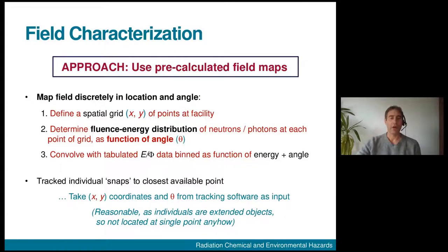So instead, the approach we used was to pre-calculate field maps. In other words, we mapped the field discretely in location and angle. So we defined a spatial XY grid of points at the facility. We determine the fluence energy distribution of neutrons and photons at each point in that grid as a function of angle.